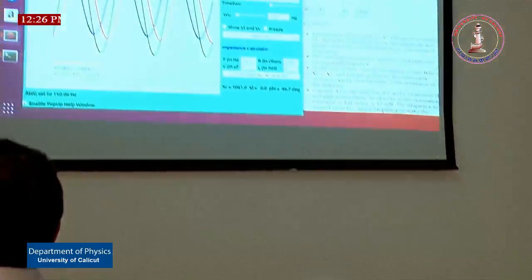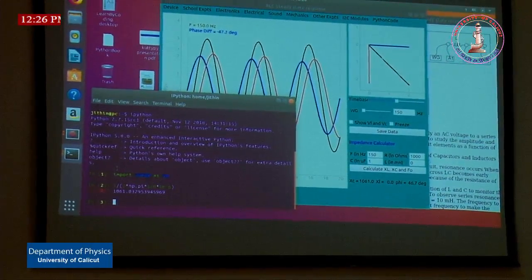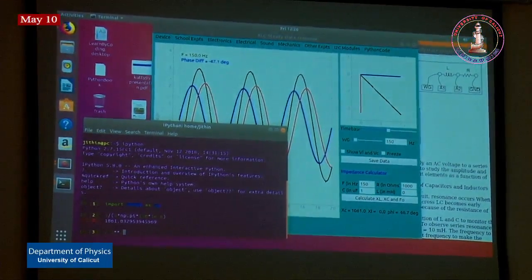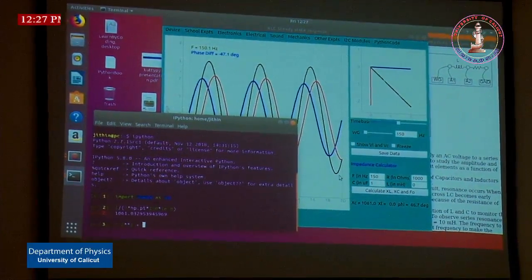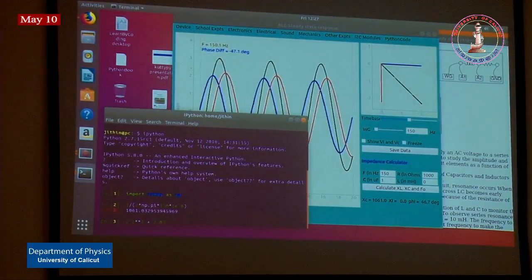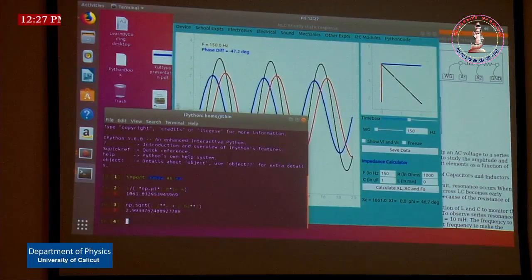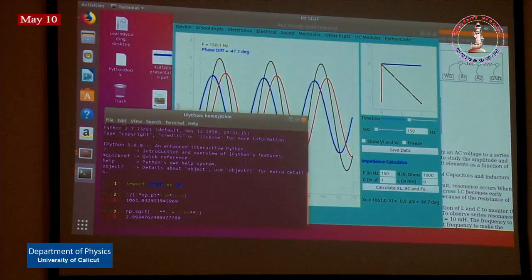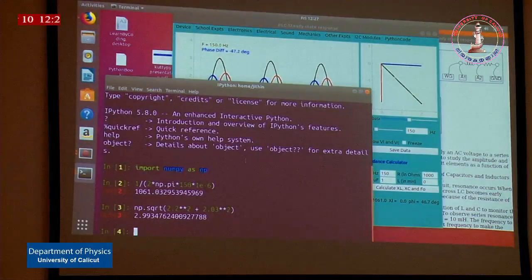You have to add them because they are not in phase, right? How do you add it? Find 2.2 squared plus 2.03 squared, and take the square root of the total. That is 3 volts. So there is nothing wrong.